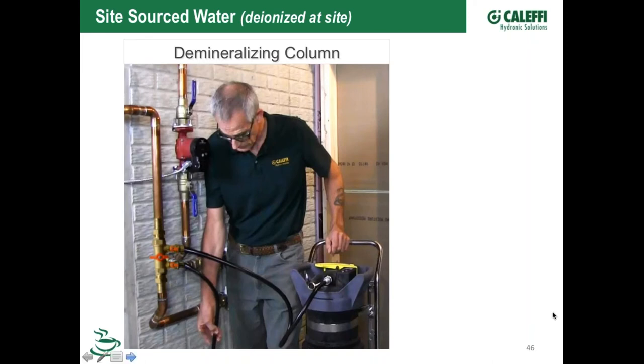So what we did in our lab in Milwaukee a year or so ago when we were developing this cart is we bought 5 or 6 different brands of low water cutoff probe types. We put them in the water as it came out of this, and we measured the TDS of the water. We found if you get down below about 10 or 12 ppm on the TDS meter, those low water probes wouldn't make contact anymore because there wasn't enough conductivity.